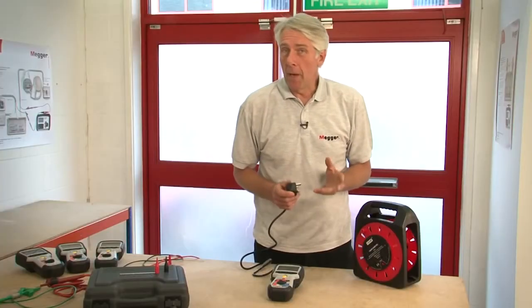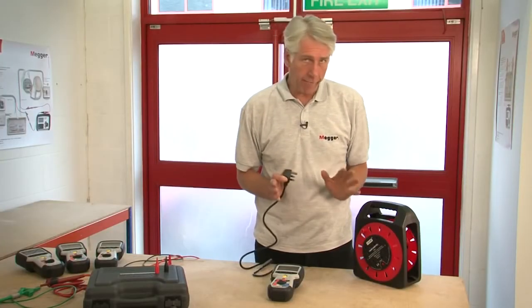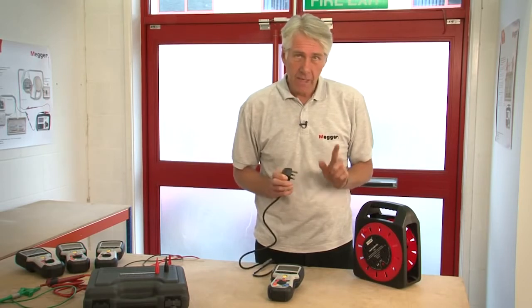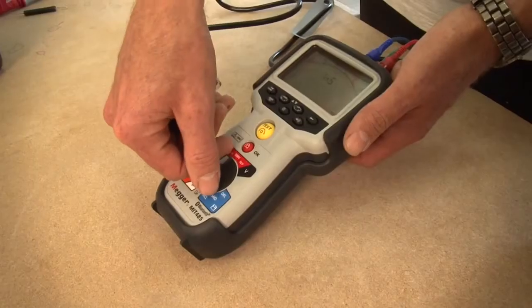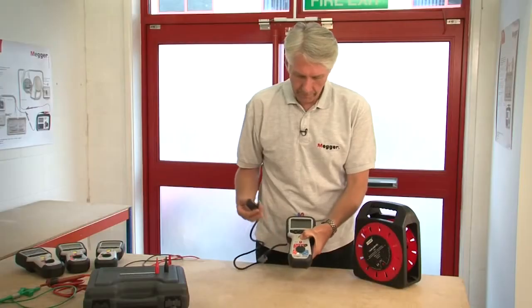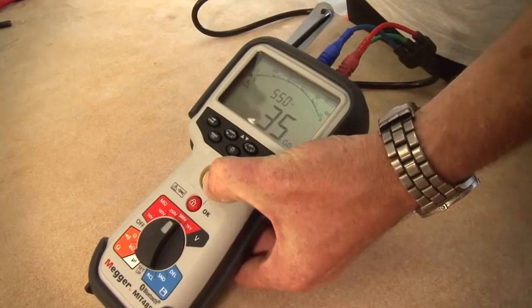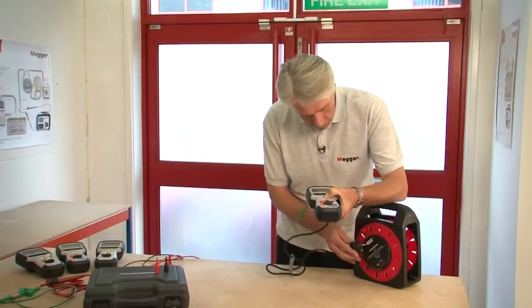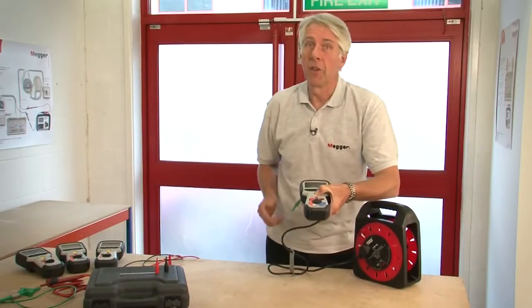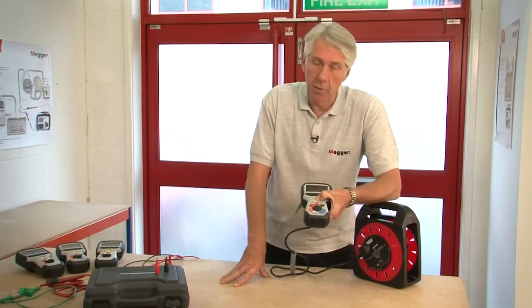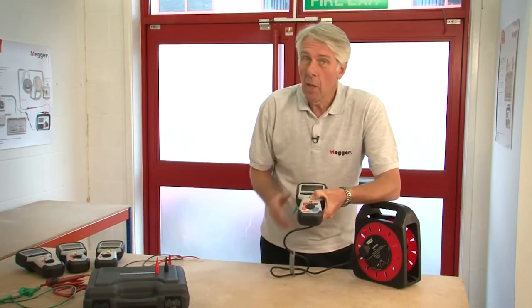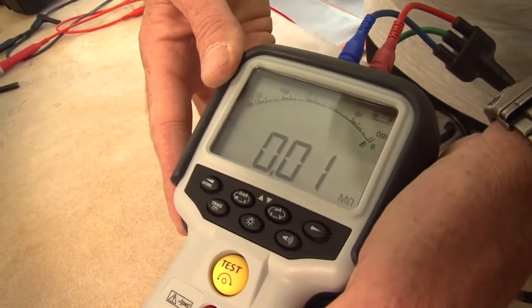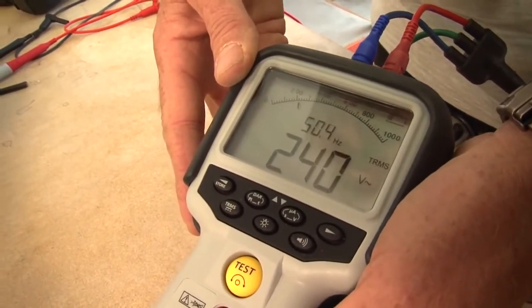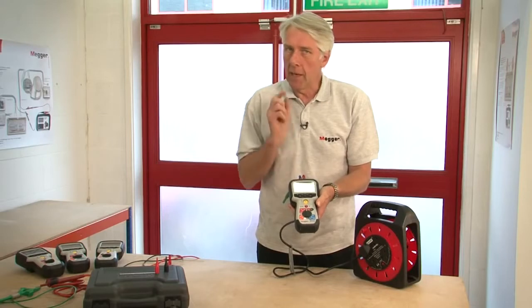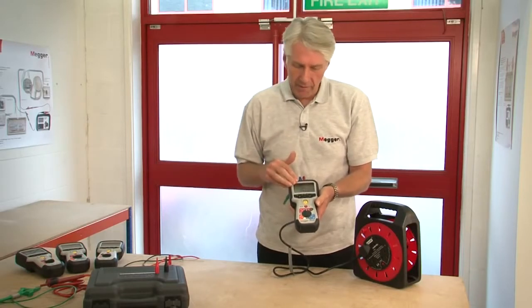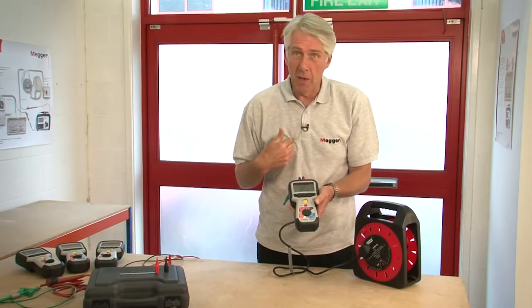Now, what makes the MIT400 series superior to virtually every product on the market is this. If I initiate an insulation test, let's say 500 volts, and that's reading a massive 35 gigohms. Now, we plug it into the mains, with the test button still pressed, and in this situation, the product is completely safe. When I let go of the test button, it actually reverts back to the voltage measuring screen with, of course, the warning buzzer. But again, most importantly, neither the product nor the operator has come to any harm.